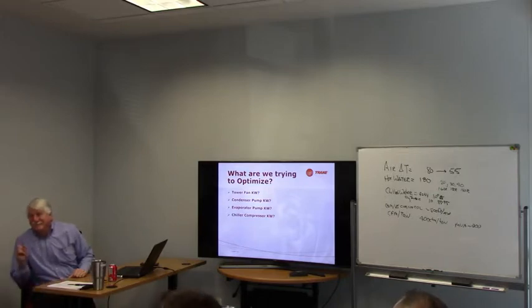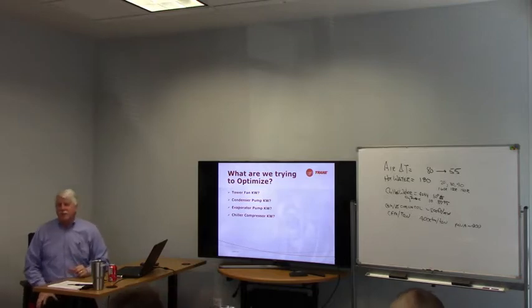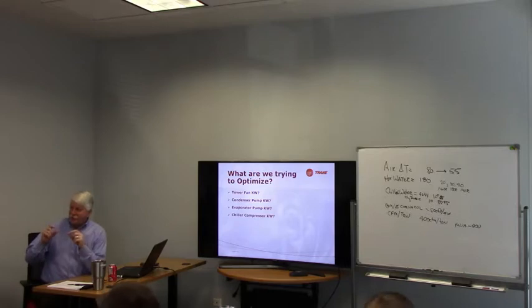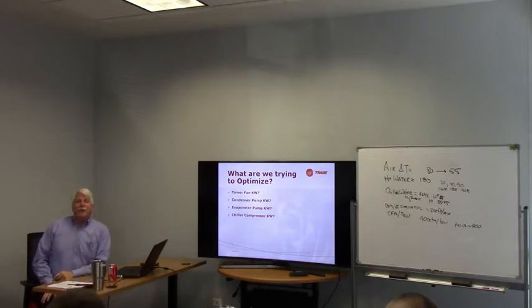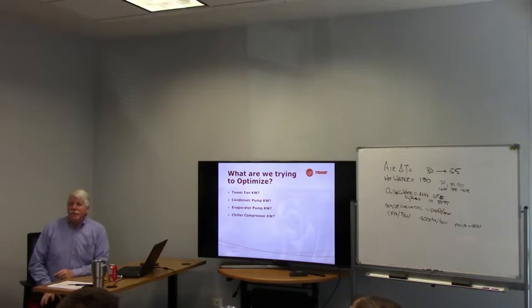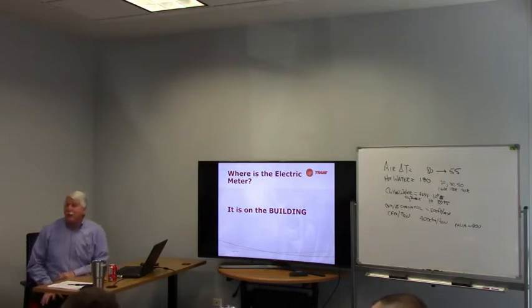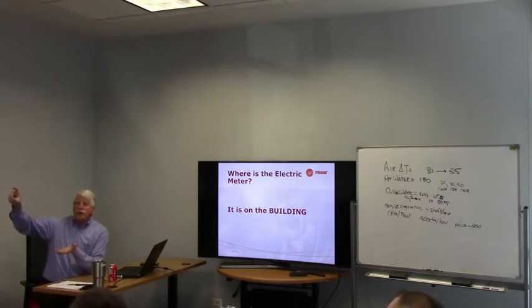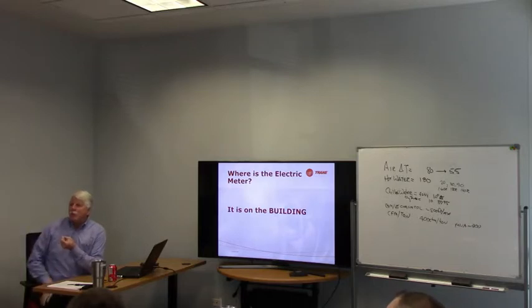All of the above. That is the right answer. The answer is all of the above. The thing we have to be careful of is especially equipment vendors will focus on the thing that they have the most effect on, okay? So a guy will tell you, well, my chiller can get down to 0.38 kW per ton. Yeah, but he doesn't tell you that his GPM is going to be twice what everybody else's is, so that pump KW is going to go way higher, okay? And the key to this is, the electric meter is on the building, okay? If you save money in one part of your system and it costs you more somewhere else, you didn't save that money, okay? Because the meter is on the building, the meter isn't on individual pieces of equipment.